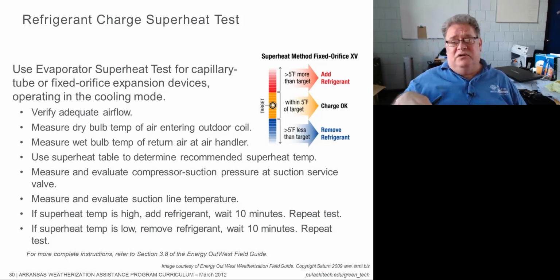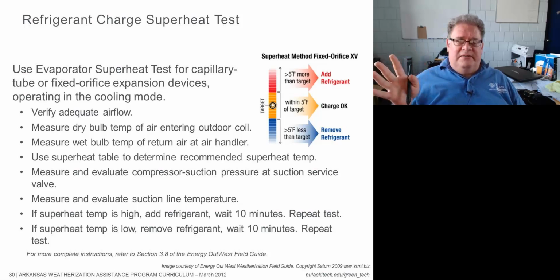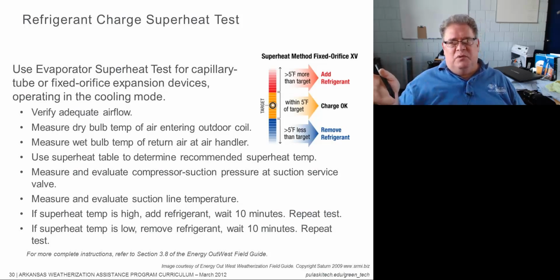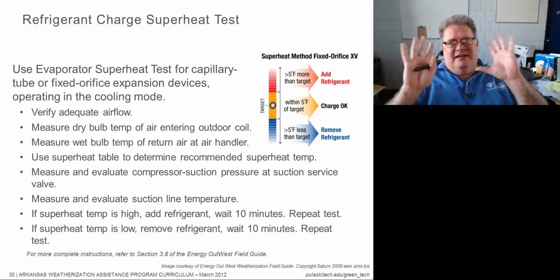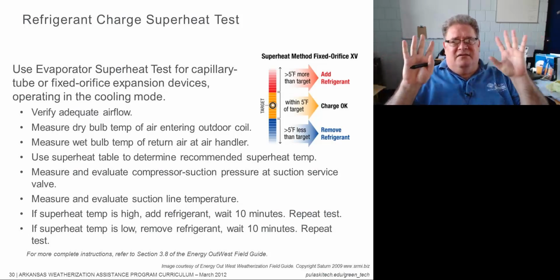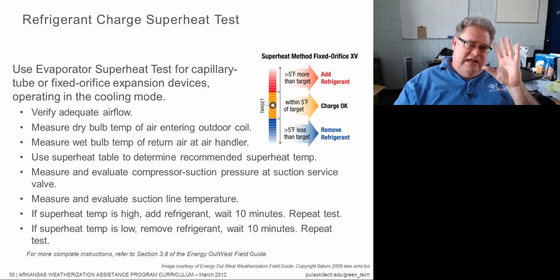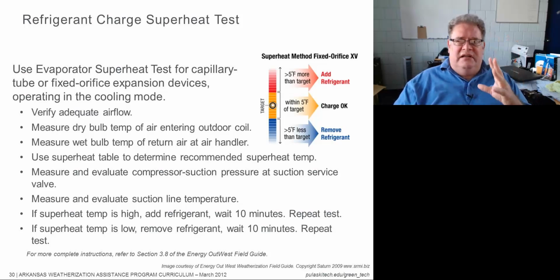We have to be running in cooling mode. Okay, we have to have adequate airflow. We need to know the dry bulb air temperature, or temperature of the air entering the outdoor coil. We need the wet bulb temperature of the return air inlet at the air handler. All right, how many of you are going, stop right there, you lost me, this is all hurting my head? You're right, it does hurt your head. It's complicated. It's not simple stuff until you've done it a lot.